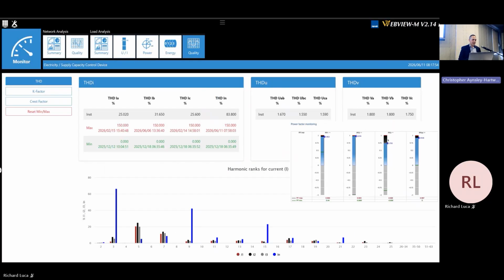So looking at the THD now, straight away down the bottom, I can see the blue chart, the 3rd, the 9th, the 15th, the triplen harmonics are quite high on this load. And the chart on the right, that's the power factor. On the 3 phases, look at the 3rd phase, something's happening there. That warrants me to investigate what's happening on that phase.